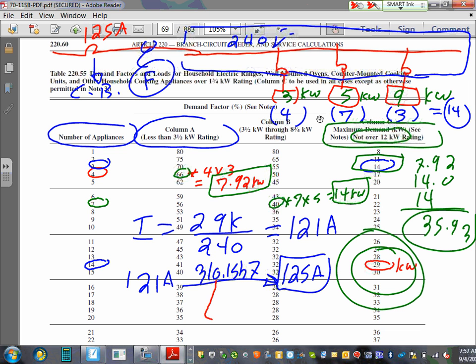The same thing from here. What's the conductor size? Let's use full neutral. 3 conductors. What's the conductor for 125 amp? Copper. Number 2. Number 2 AWG. Done. That's what you guys do. So we size the feeder. This feeder is number 2. The conductor, 3 of them. Why 3 of them? 2 hots and a neutral. We could derate the neutral. They allow you to derate the neutral.